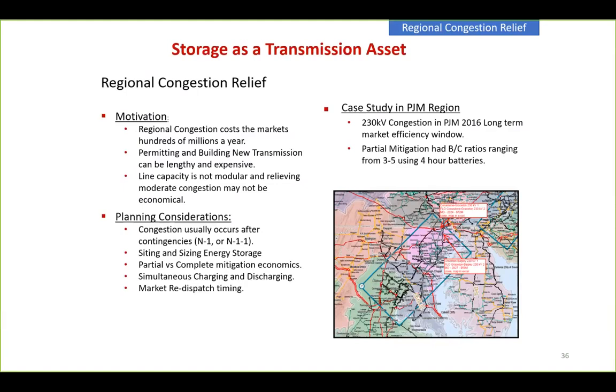This was looking at 230 kV congestion in PJM and where we could relieve congestion with batteries. Two key points: congestion usually occurs after the N-1, the first contingency. Money is spent every day, 24 hours a day, to avoid overload in the what-if case—redispatching off economics so that if an outage occurs, you won't have another overload. If you can deploy a battery that responds almost instantaneously to shift power flows in the event of the outage, you avoid the congestion costs all year, and the battery only has to operate during the event. It's a very attractive application for storage.